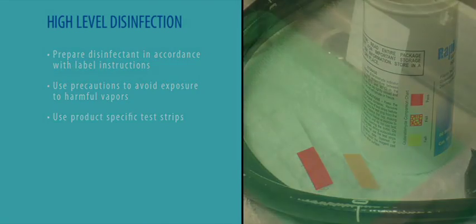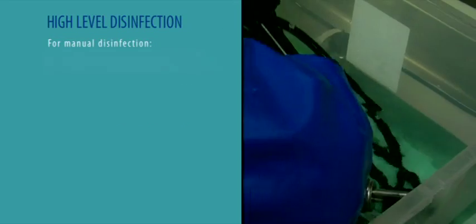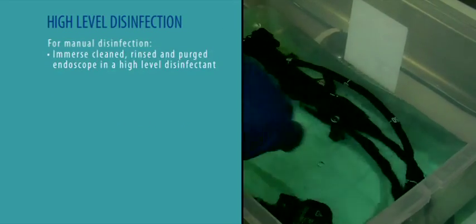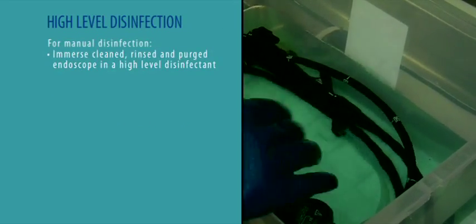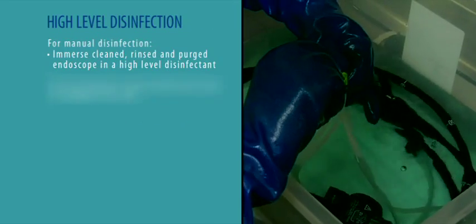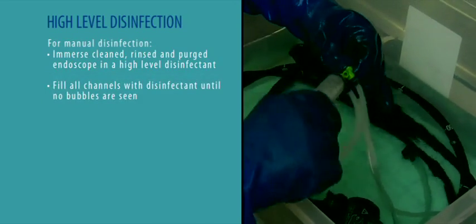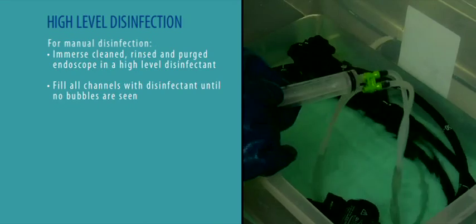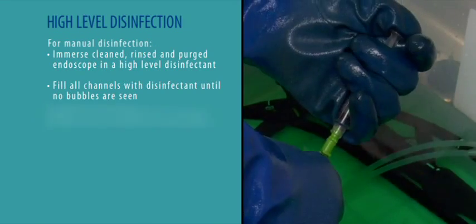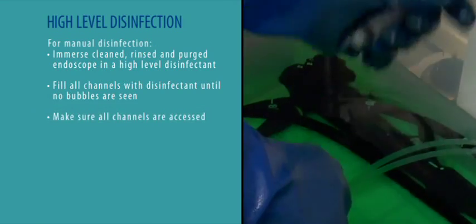Reusable HLD sterilants must be changed whenever the MEC fails or the reuse life expires, whichever comes first. For manual disinfection, immerse the cleaned, rinsed, and purged endoscope in a high-level disinfectant. Fill all channels with disinfectant until no bubbles are seen exiting the opposite end of each channel. Make sure that all channels are accessed.